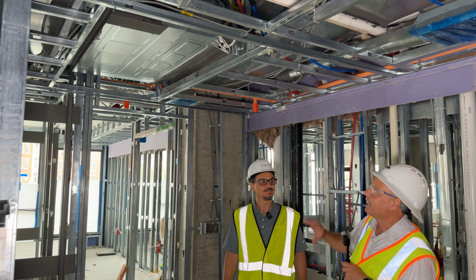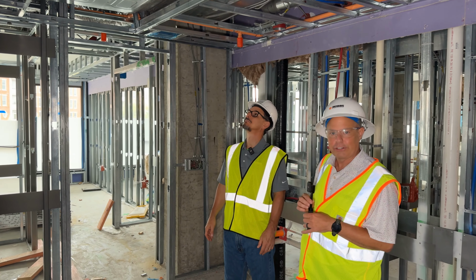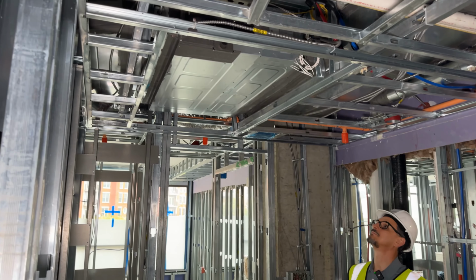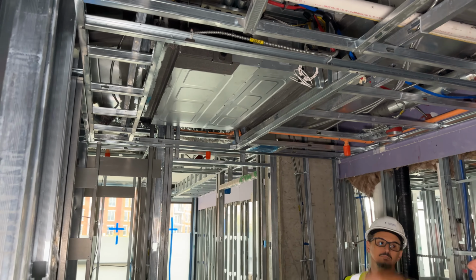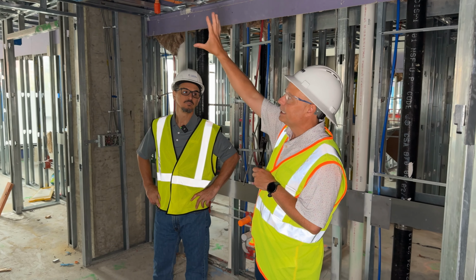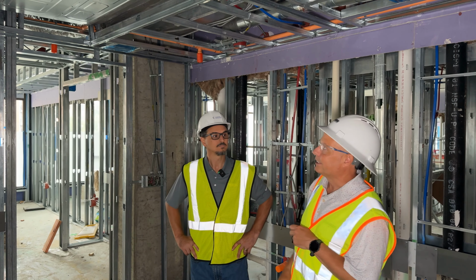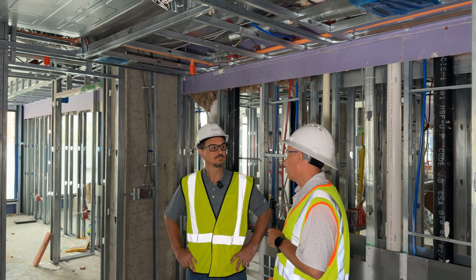One of the things that is unique about the DC area is we have a height limit of buildings, which is 130 feet typically. So as you'll see, our plenum space is probably one of the smallest you'll see in the country, and typically most owners want 1 foot or less for their plenum space. So having these nice thin boxes really is a great benefit. And with the medium static duct, you actually have enough fan power to also have some ductwork to distribute it. So you kind of get the best of both worlds of having your fan power as well as meeting this nice thin duct requirement that we have here in DC.